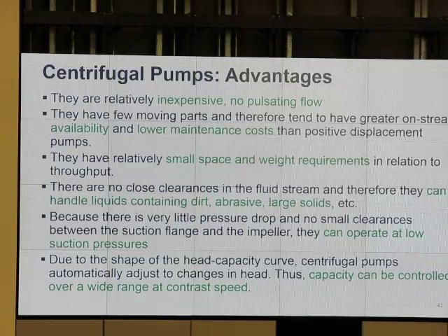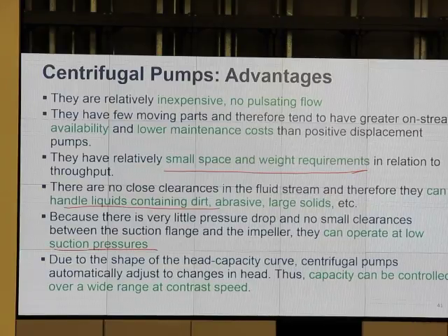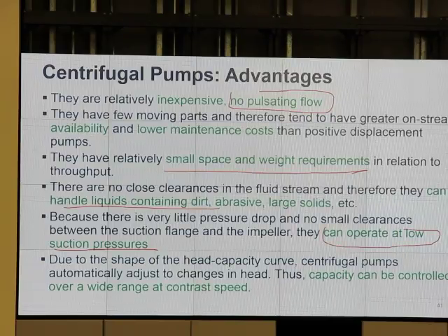Centrifugal is less efficient compared to PD pump. Inexpensive or something. Just focus on this green part and you should be able to tell at least 2 or 3. So tell me 3 advantages of centrifugal pump. You may say no pulsating flow. You may say it can operate at low suction head. You may say it can handle some solids. If you have 3, maybe it's good enough. Or if you can have all, it will be very good, but maybe 3 is good enough.